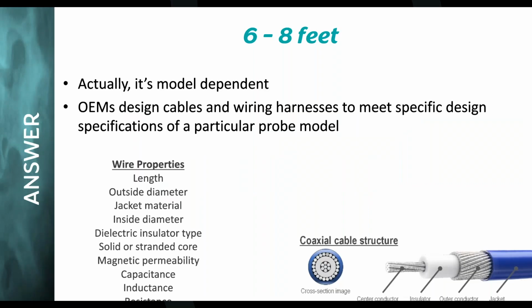There's a common practice within the industry. Typically, probes will break, kind of like your iPhone cable. If this is the scan head and this is the probe cable, you're constantly doing this, and so the cables start to break in here. So what some companies do is what's called a cutback. They cut this section out and then resplice it and shorten the cable. It'll work, going back to getting probes working again versus OEM form, fit, function. We do not alter the length of a probe cable by more than probably 3%, which is about our limit. And if we can't do that, we fabricate a new cable.